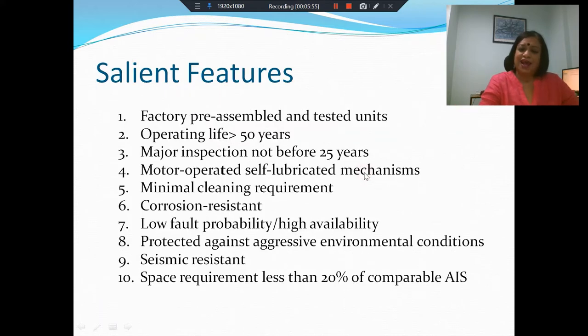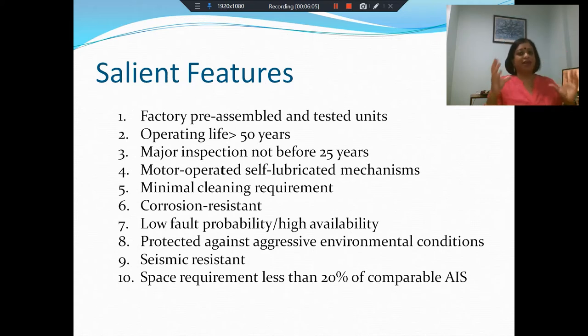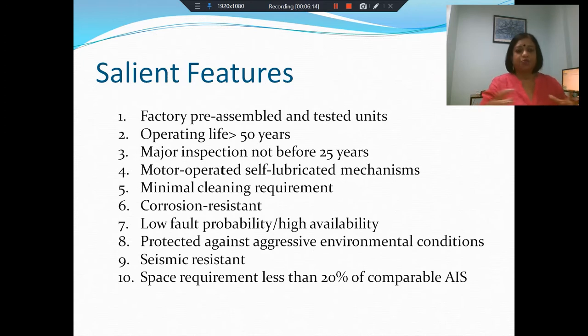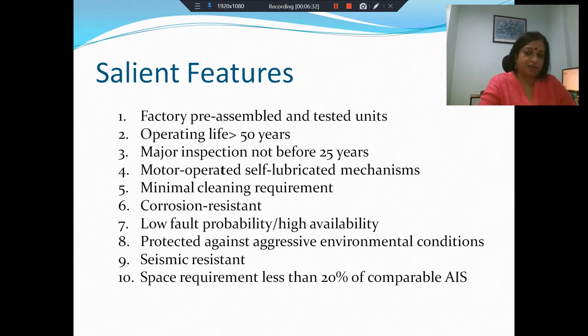What are the salient features of gas insulated substations? We need enclosures — everything goes inside the enclosure and it is like a module. The gas insulated substation is factory pre-assembled and is a tested unit. You buy it as a unit and then assemble various modules on site. The operating life tends to be greater than 50 years, and you don't even need a major inspection before 25 years.